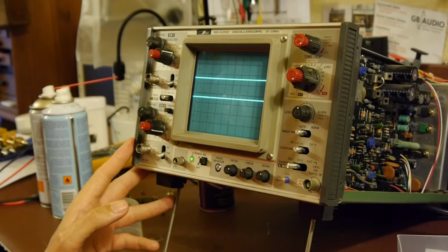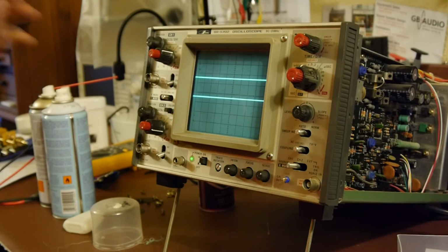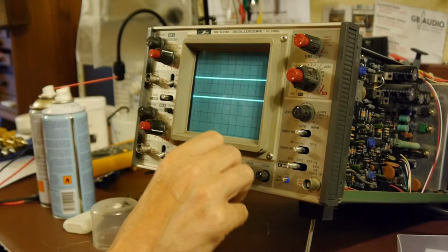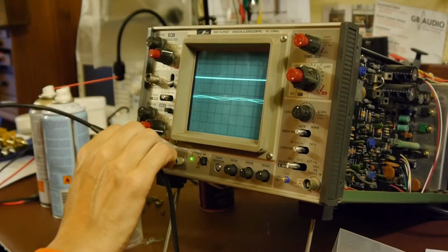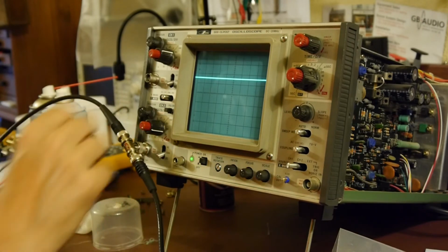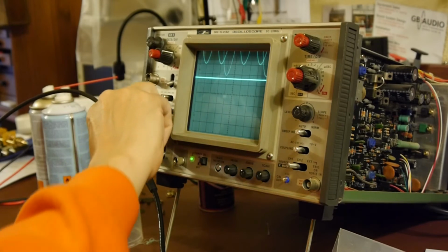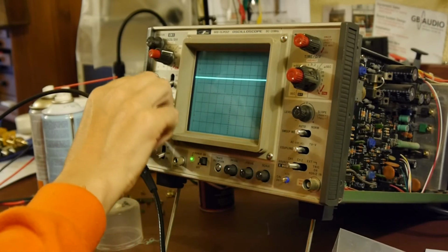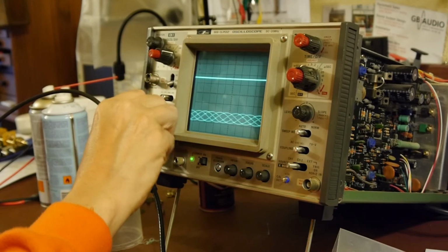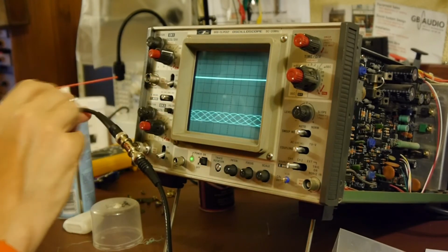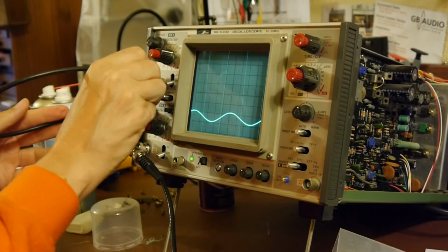So I'm thinking that perhaps it would be worth going through the calibration routine for this, because this equipment wasn't originally assembled like this. Okay, so we've got two traces up. That's something, isn't it? Intensity seems okay. So let's plug our signal in now. Oh, got something there on channel 2. Let's get channel 1 on. Something there on channel 1.